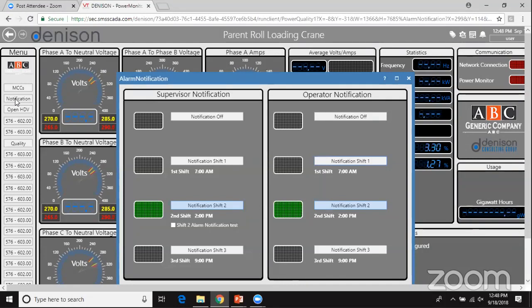I can then allocate who on my shift is to receive what alarm, when and how. For example, I have 3 shifts in this, and based upon those parameters I configure myself, my roster of employees will receive either alerts that are yellow, or alarms that are red. Certainly I don't want an alarm flooding situation. If I'm the controls manager, I don't want to see it all, but I do want to see when things start to go really, really bad. And again, going back to the slippy map, the geographic map I showed you, we can support an unlimited number of data sets and an unlimited number of users on this platform.